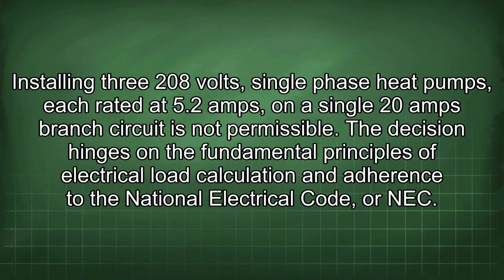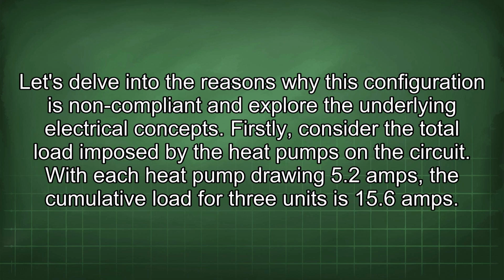Installing three 208 volts, single-phase heat pumps, each rated at 5.2 amps, on a single 20 amps branch circuit is not permissible. The decision hinges on the fundamental principles of electrical load calculation and adherence to the National Electrical Code, or NEC. Let's delve into the reasons why this configuration is non-compliant and explore the underlying electrical concepts.